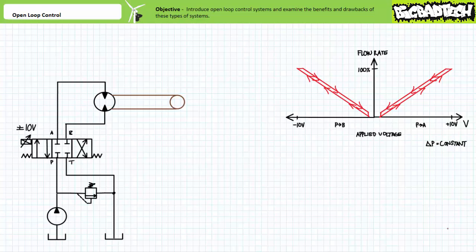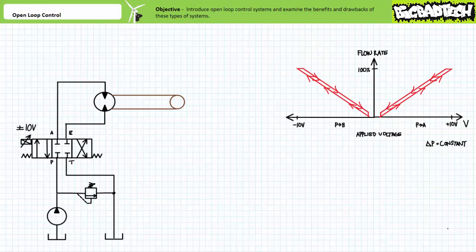We'll simplify the user interface as a proportional valve controller that simply issues a voltage signal to the proportional valve linear force motor. Additionally, we'll assume that the proportional valve makes use of internal closed-loop control of spool position by making use of a spool position feedback sensor in the form of a linear variable differential transformer. Hysteresis between observed flow rates as voltage is on the way up versus on the way down still exists, but it's not nearly the problem one might observe without this means of internal closed-loop control of spool position.